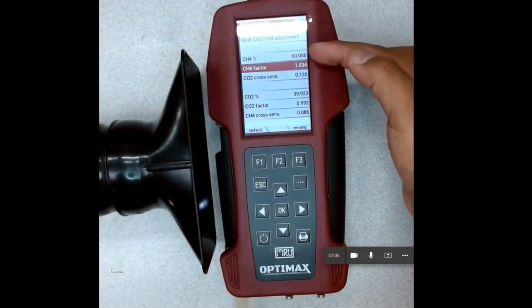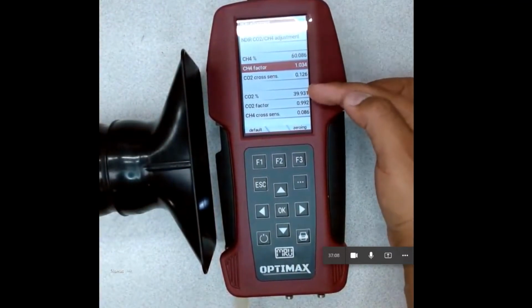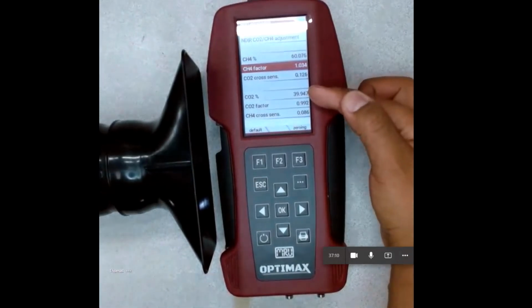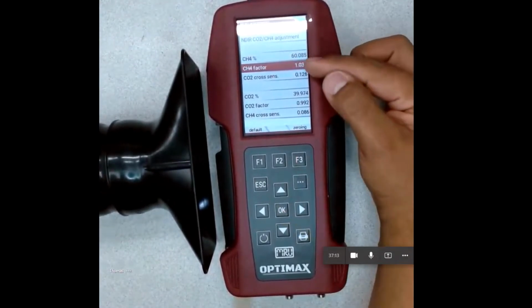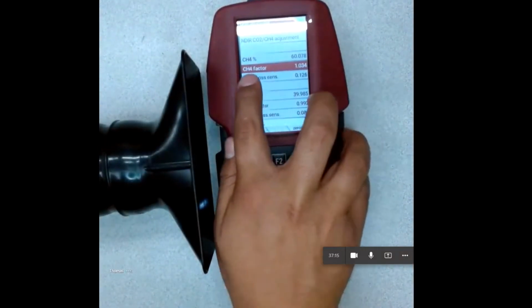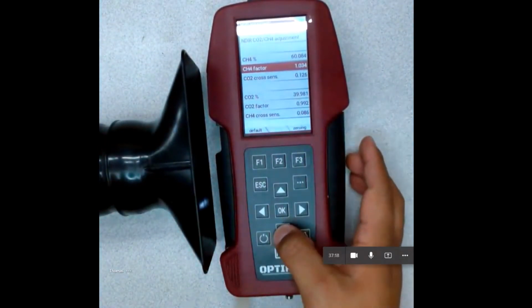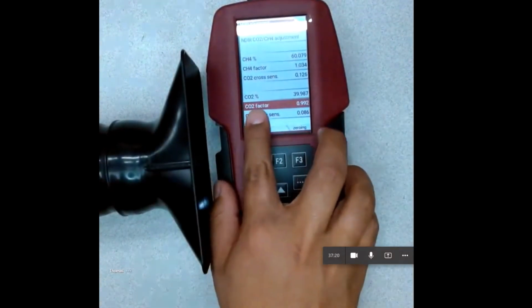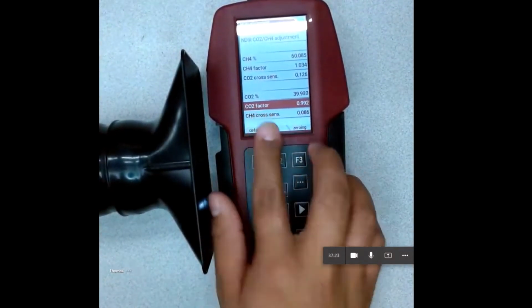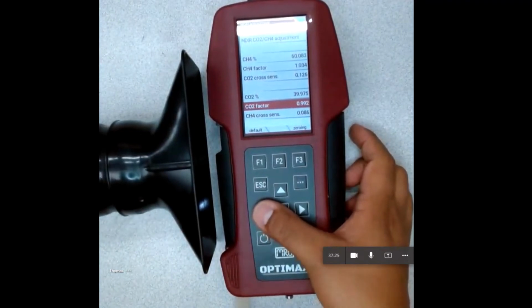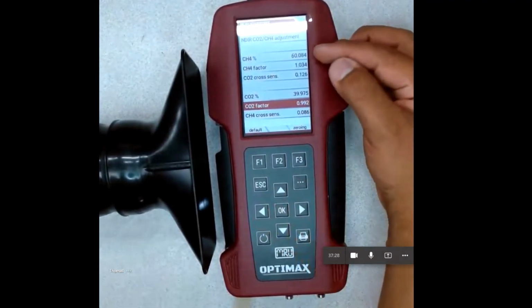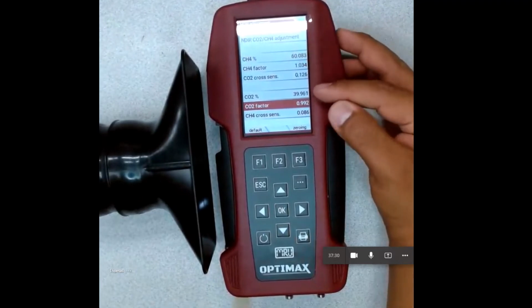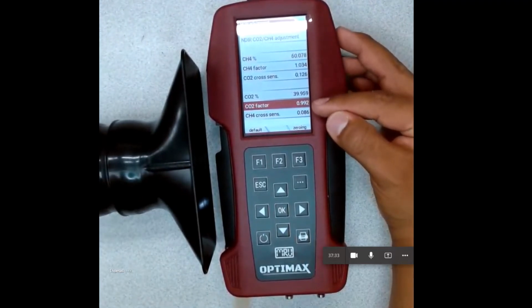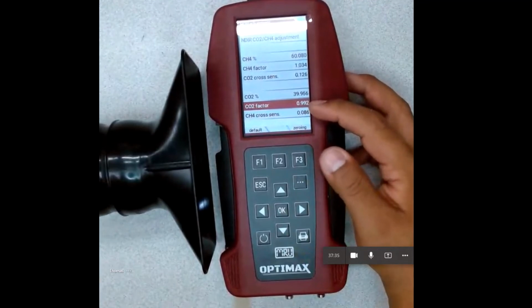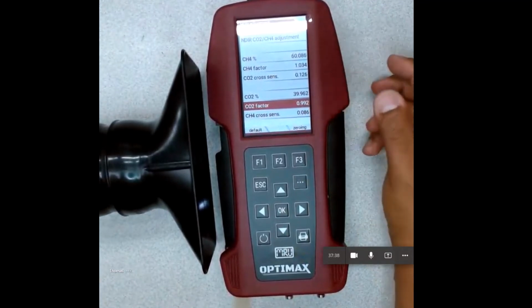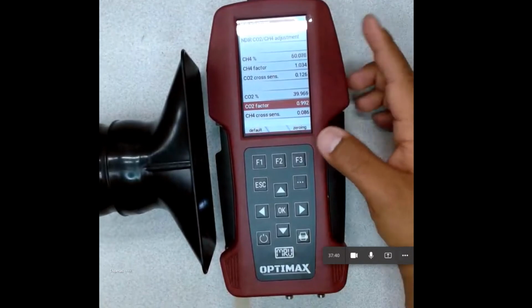So now we've got methane, CH4, and carbon dioxide, CO2. And we'll only use the factors. So you see this has CH4 factor. We'll change that number. And we'll change this number, CO2 factor. And we'll just put those numbers until they match what's on the bottle. So these are the values that it's reading: methane percent, carbon dioxide percent, and then these are the factors that it's using. So we'll have to adjust these until they're at the right value.